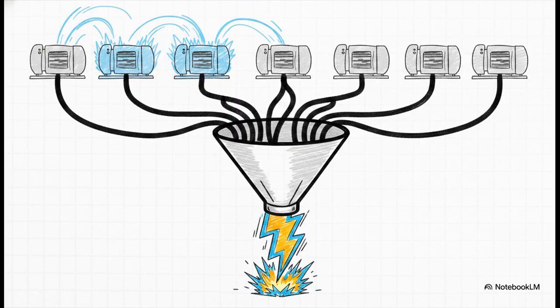And that brings us to a pretty terrifying reality about marine power plants. We're talking about the sheer scale of the danger here. The fault contribution stacks with every single source you connect to the busbar. It's entirely cumulative. And here's the detail that catches a lot of people off guard. It absolutely does not matter if that generator or motor is just idling or barely carrying any load when the fault happens. If its breaker is closed and it's electrically connected to the bus, its full short-circuit power contribution gets dumped straight into the fault. The grid basically acts like a giant funnel, directing all that potential energy right into the short circuit in literally milliseconds.